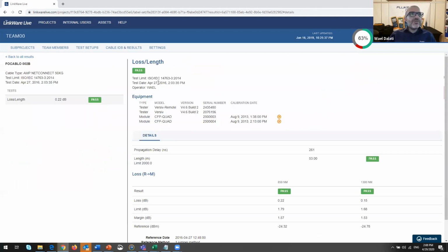So this test was done, let's say, forget about the date, but it was tested in 2016, while the calibration date of the machine was 2013. And you have an immediate flag next to it. It's past the recommended calibration date. So Linkware Live helps you spot if your tests were done out of the calibration date. You will be able to see it and spot it. But whether it will be approved by the manufacturers is not in our control. It is back to the manufacturer whether they will approve these kinds of tests for warranty.